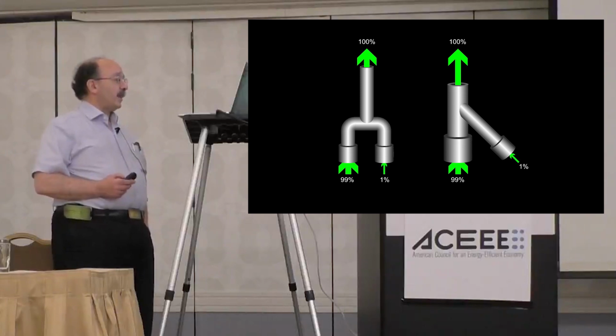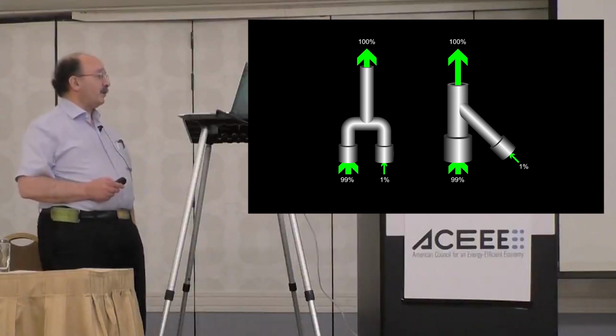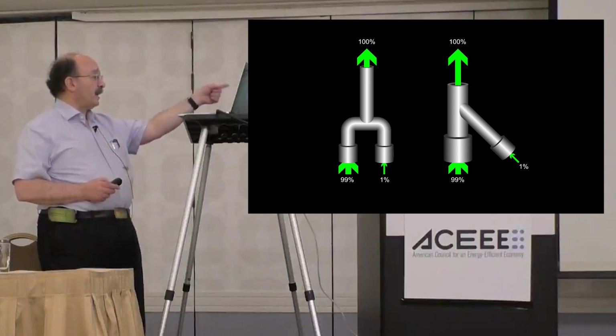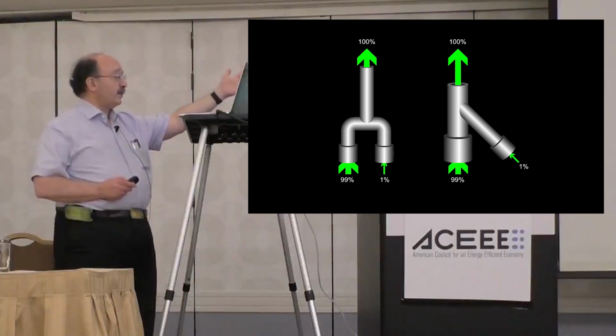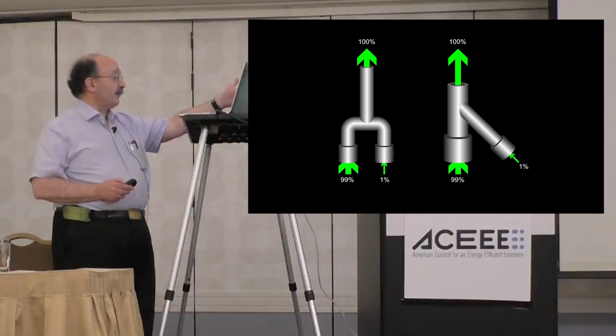The design changes we need are so simple you can grasp them just from a sketch or a photograph. In practically every building and factory, a critical pump with an in-place spare is laid out so the flow always goes through 2 right-angle bends. Friction. Why not lay it out so the main flow has no bends and also fewer valves?